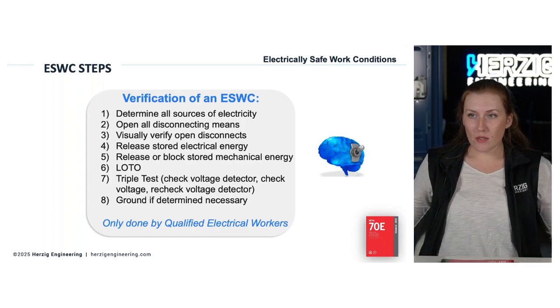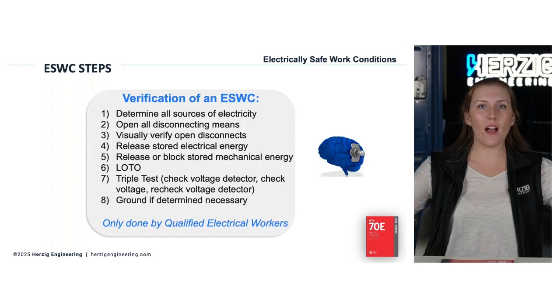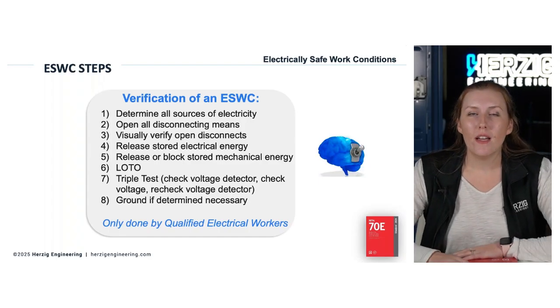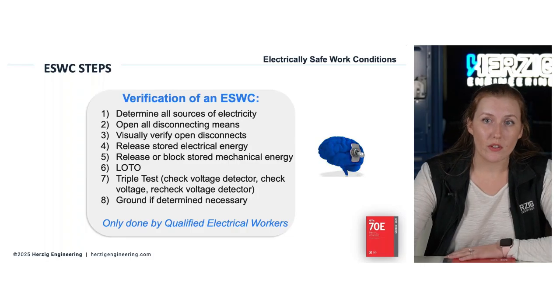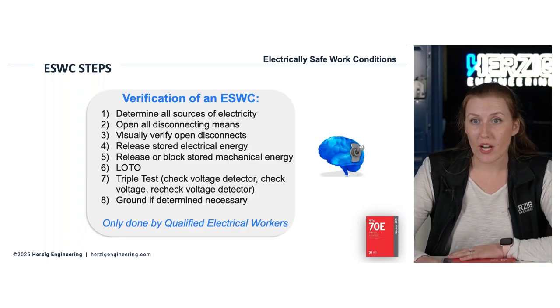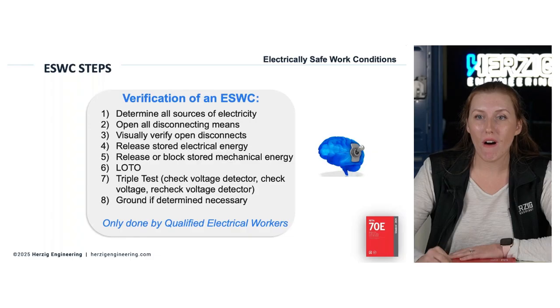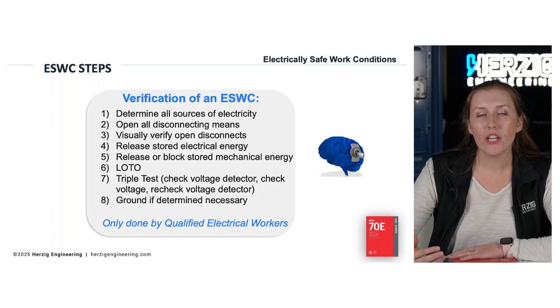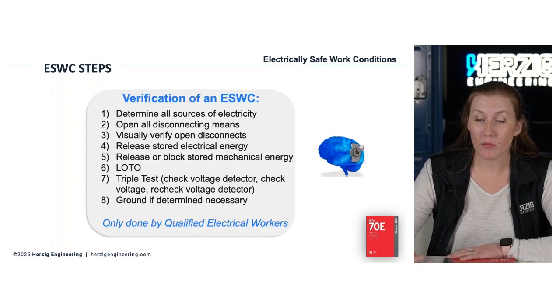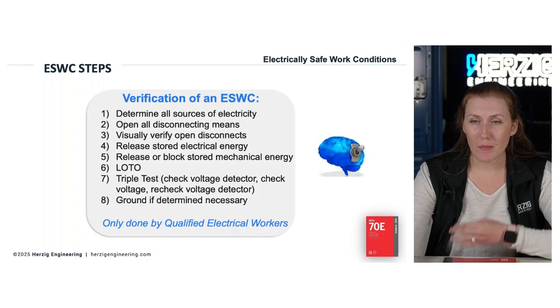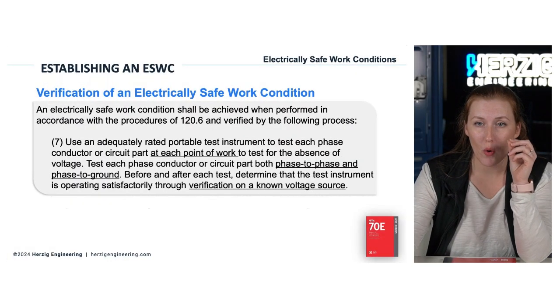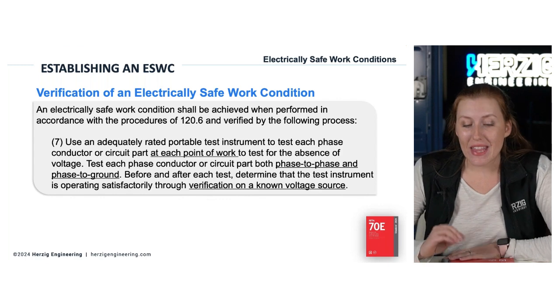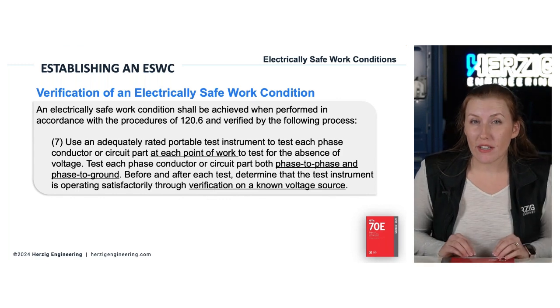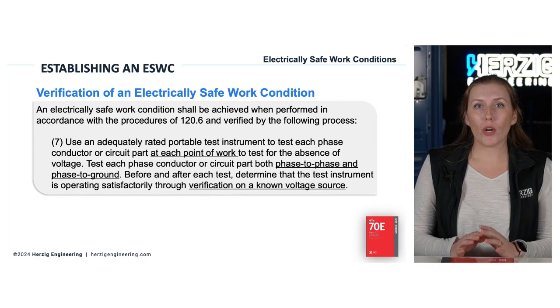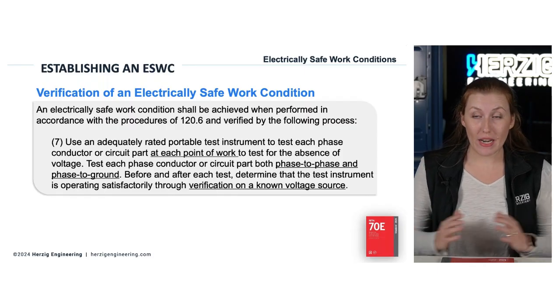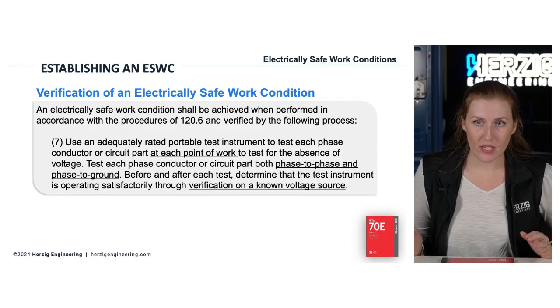And a lot of times that's where people stop. They're like, okay, locks and tags are on, let's get to work. Step number 7 is so critical. Live, dead, live. Do your triple check, make sure that it actually is off, and then if necessary, you're going to apply temporary protective personal grounding equipment. But that step number 7 really is so pivotal. And this is the step, even if you know you need to verify absence of voltage, a worker might not do it thoroughly, may not actually do all the elements of step number 7.